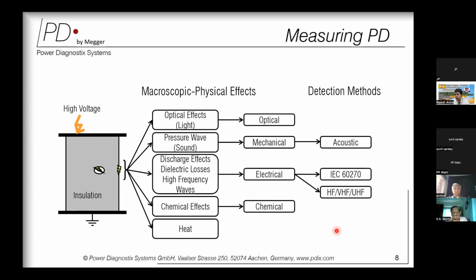When we need to measure partial discharge, we need to use some detection methods. Whenever partial discharge occurs in any insulating material for whatever reasons, it gives birth to various physical phenomena, which can be detected using various detection methods like optical, mechanical, electrical or chemical. But not all the methods are useful for measurement of partial discharge. Suppose we take an example of the optical method. In this method, the optical detector will definitely measure the light or the spark generated by the partial discharge, but the optical detector in this case has to be close to the phenomenon, that is, it has to be close to the source of light.